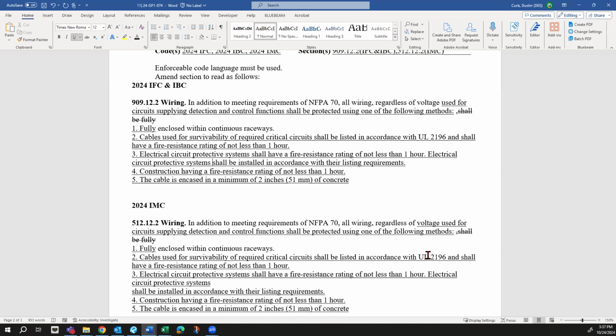Like if you had a pressurization system in a fire alarm system, you only have to have smokes outside the smoke-proof enclosure. You'd have to have detection for the water flow switches. But if there's a lot of smoke detectors there, or a lot of other devices that are part of a fire alarm system, they shouldn't be required to be in a raceway when they're not there to serve the purpose of the ventilation system or the pressurization system. And that's kind of what the 2027 ICC proposal was. We just took it, Kimberly and I worked on this, and just basically took that verbatim and carried it over and presented it this way.